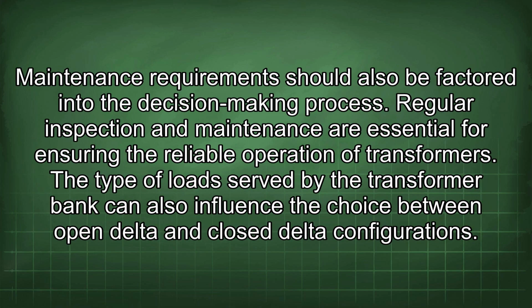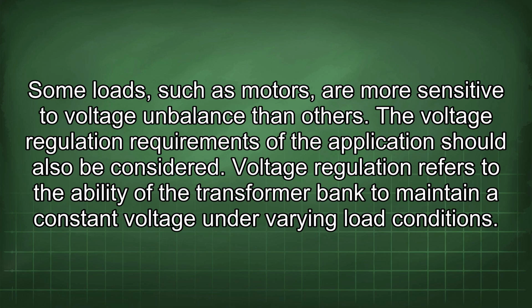Maintenance requirements should also be factored into the decision-making process. Regular inspection and maintenance are essential for ensuring the reliable operation of transformers. The type of loads served by the transformer bank can also influence the choice between open delta and closed delta configurations. Some loads, such as motors, are more sensitive to voltage imbalance than others.